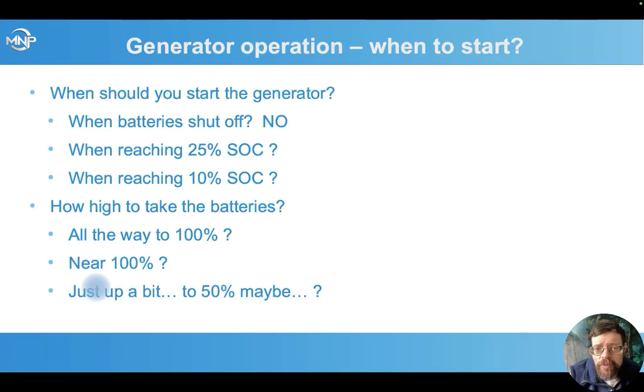So it really depends on what the situation is, how high you want to go. But what we see a lot is long periods of dark, cloudy weather, and everyone's just kind of bouncing between 25% and 50%, long enough to keep it going for the next night, and then they've got to run it again. That's really not the best way to do it. Better to just let it run for longer and charge it all the way up. However, considering that we don't want to run for too long on our air-cooled generators at one time and risk overheating the generator, there are some competing things there.